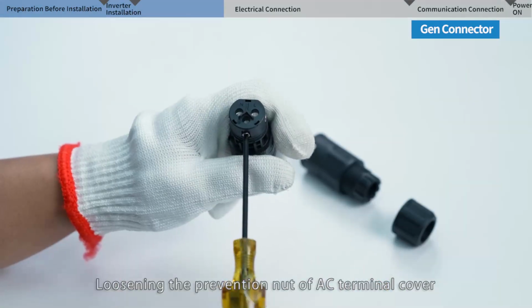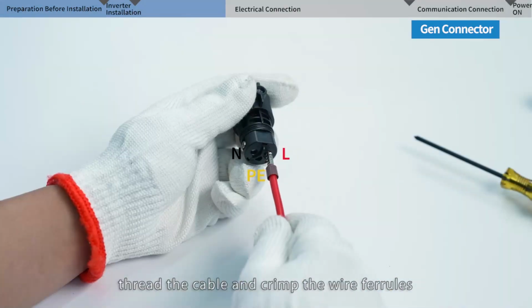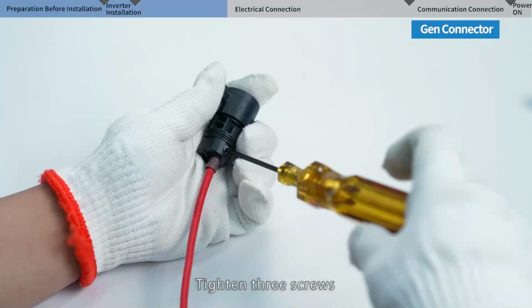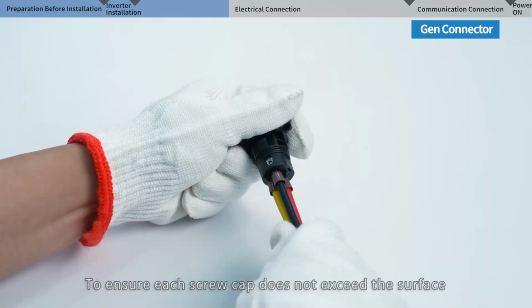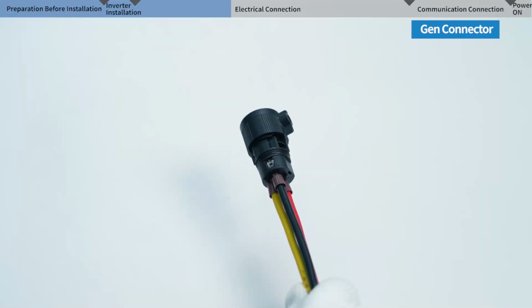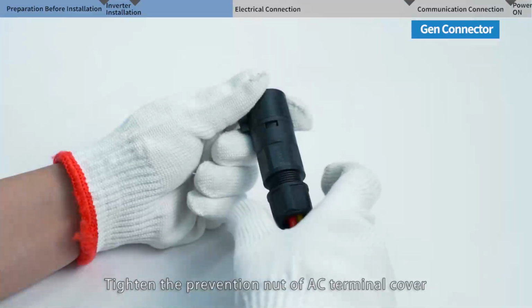Loosening the prevention nut of AC terminal cover. Thread the cable and crimp the wire ferrules. Tighten 3 screws to ensure each screw cap does not exceed the surface. Tighten the prevention nut of AC terminal cover.